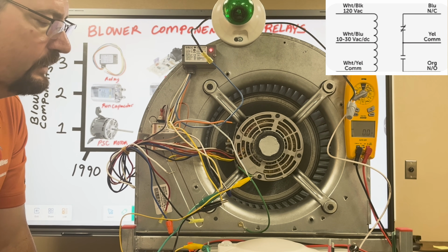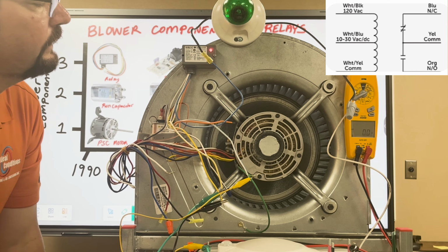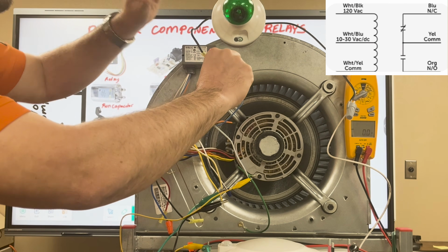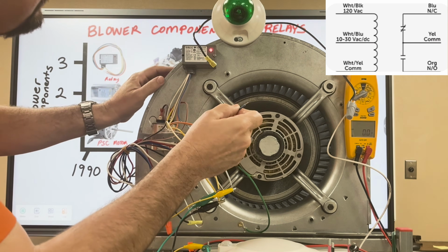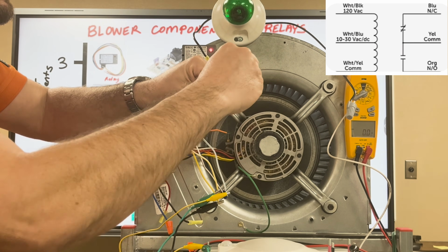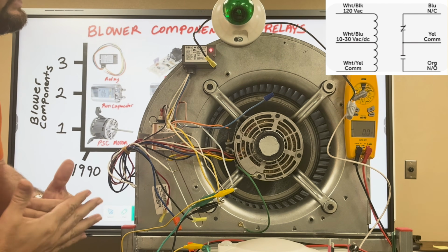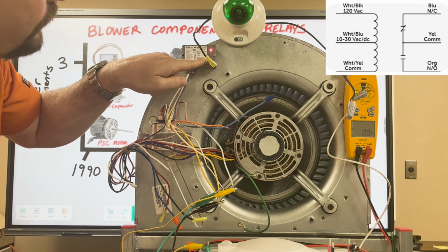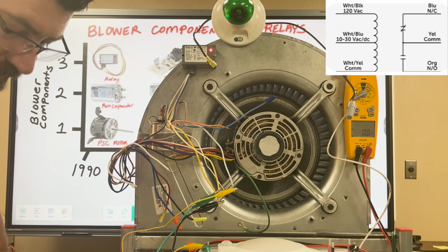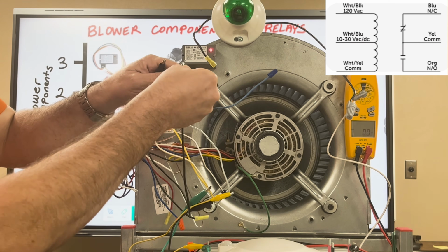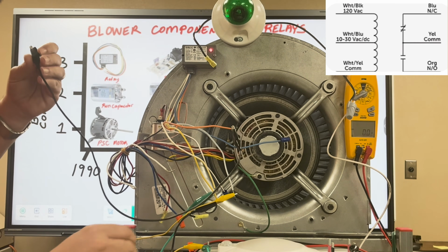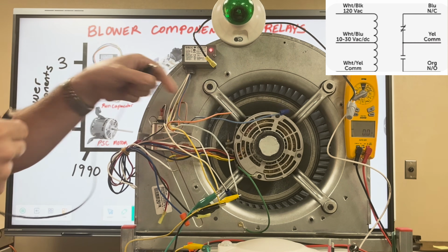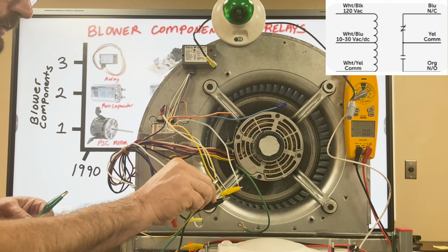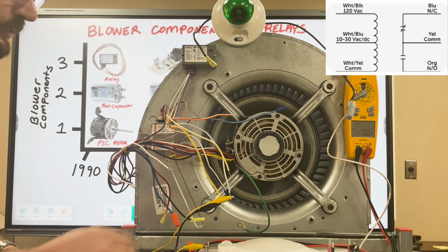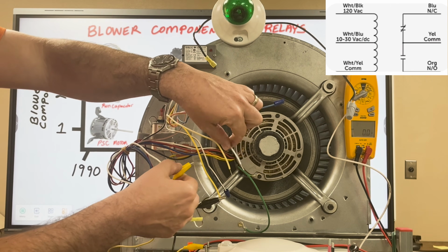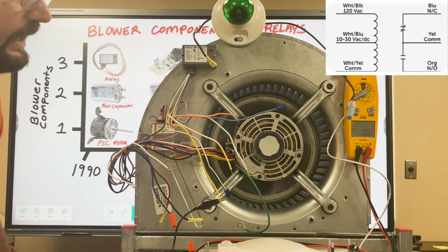Of course, the motor is going to need a second leg of power if we do it there. Let's go ahead and unhook the light bulb. We're going to cap blue off. All right, remember the solid colors, these are our contact side. We're going to wire our motor obviously to the orange, which is normally open. So we're going to take orange and wire it up to common. Let me get some of these other wires out of here just so it's not too confusing. Just like in your equipment, there are wires running all over the place, so you have to be very careful to inspect everything to make sure that you don't cross paths.